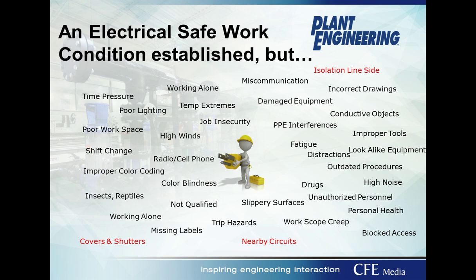One of the most important safe work practices when working on or near energized electrical equipment is to establish an electrically safe work condition. That's when you identify the sources of power, operate isolation devices, lock them out, verify isolation with testing, and you may even apply temporary grounds on certain equipment.